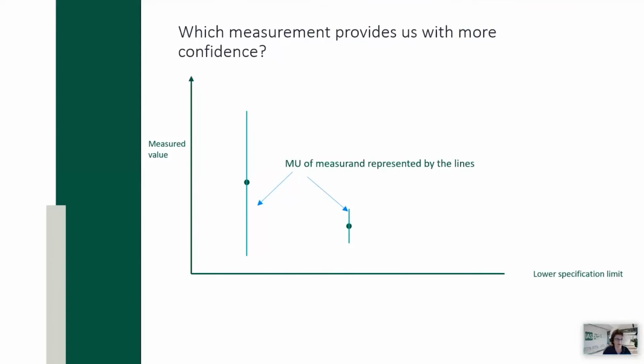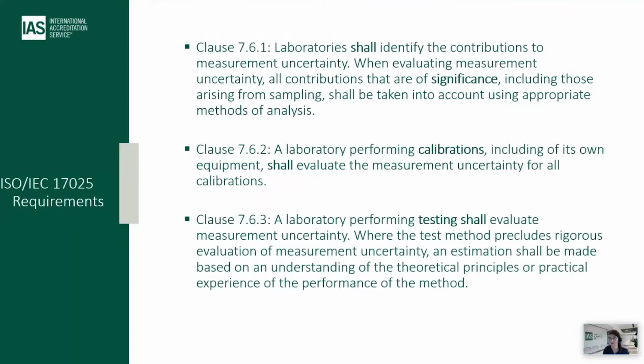So let's just quickly visit the ISO IEC 17025 standard and its requirements for measurement uncertainty, because I suspect that's why most of you are interested, because you are an accredited lab or you want to become an accredited lab. So the standard has three clauses that deal with measurement uncertainty directly. The first one is 7.6.1, which applies to both testing and calibration laboratories. And it says here quite clearly that the laboratories shall identify the contributions to measurement uncertainty. And when evaluating measurement uncertainty, all contributions that are of significance, including those arising from sampling, if you do sampling, shall be taken into account using appropriate methods of analysis. And we'll get back to that in just a moment.